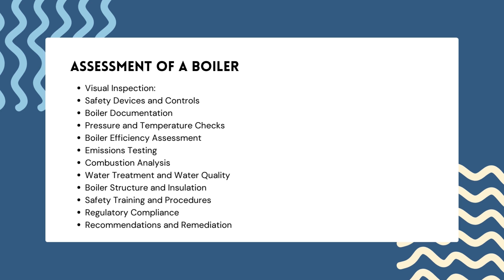Eighth, water treatment and water quality: assess the quality of boiler feed water and check for signs of scaling, corrosion or excessive deposits. Ninth, boiler structure and insulation: inspect structural integrity and insulation for signs of deterioration or damage. Tenth, safety training and procedures: ensure operators and maintenance personnel are adequately trained in safe boiler operation and emergency procedures. Eleventh, regulatory compliance: verify that the boiler complies with all local, state and federal regulations, including safety codes and emissions standards, and address any non-compliance promptly.